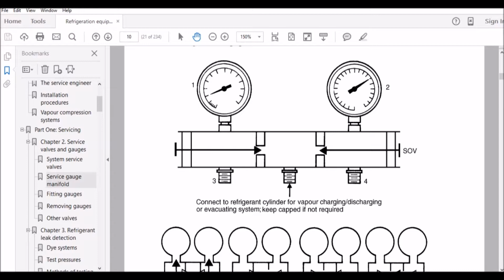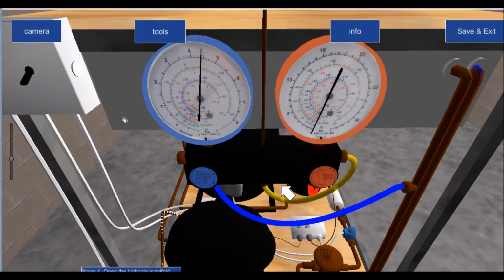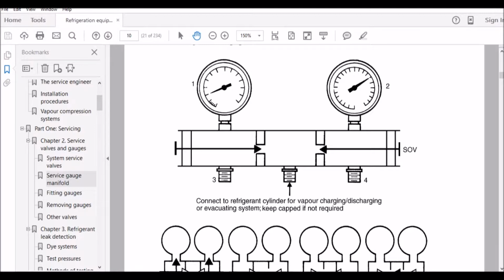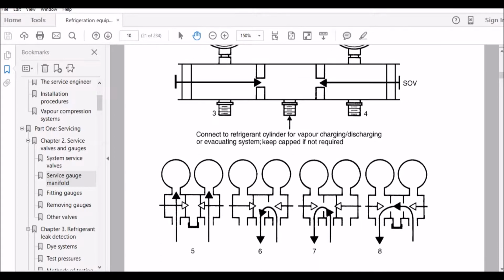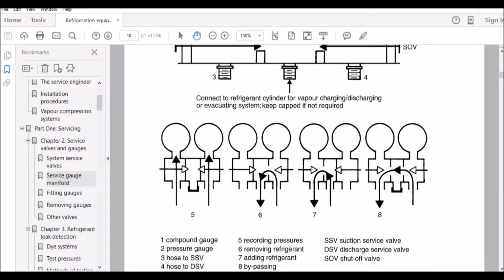Now the next thing that I have to do is open this side. By opening this shut-off valve, the refrigerant has now entered into the high side chamber, and that's why we had 4 bar registered on this side and 4 bar registered on this side on our simulator. Okay, so it's shown down here a little bit more. You can see when the shut-off valves are in the closed position, refrigerant will only go into the respective gauges, or will enter through the respective gauge ports.